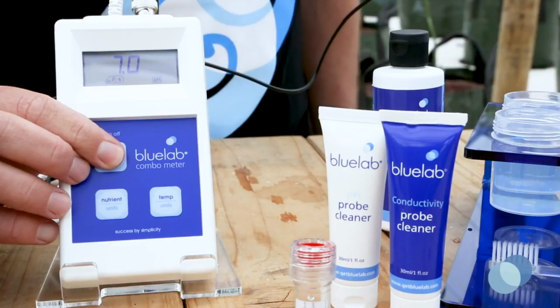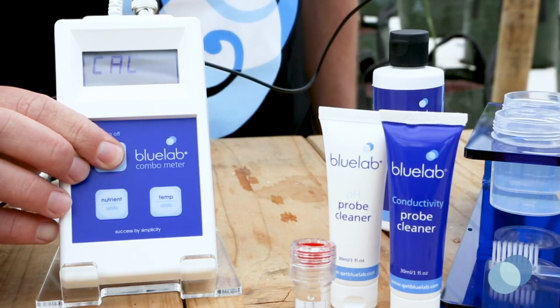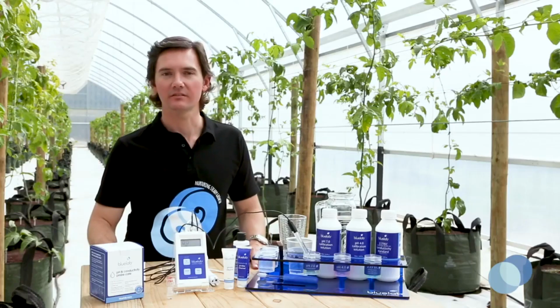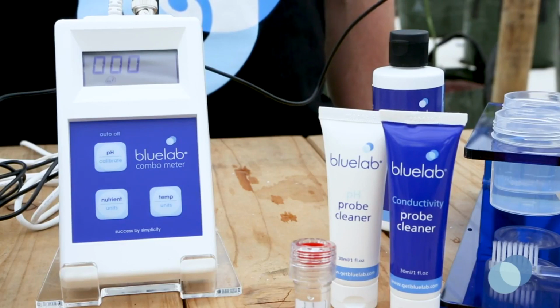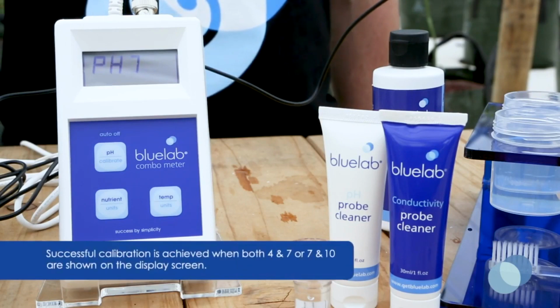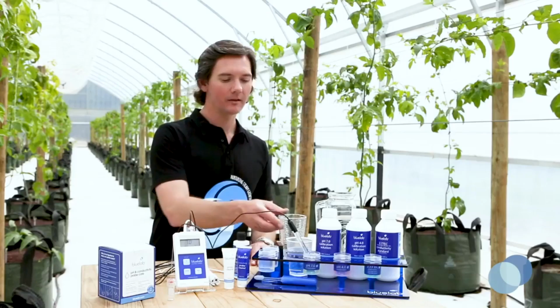Press and hold the Calibrate button until CAL displays on the combo meter screen, and then release your finger. You'll see a series of flashing symbols on the screen letting you know the calibration process is taking place. The pH 7 calibration indicator will now appear on the display. You'll see the pH 4 calibration indicator flashing, letting you know it's time to calibrate in pH 4 solution.